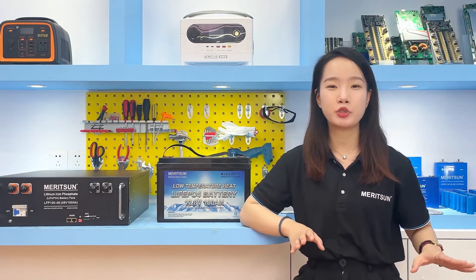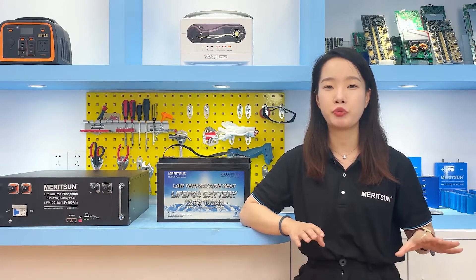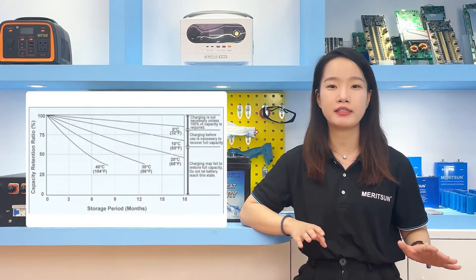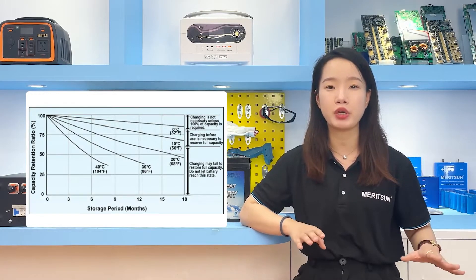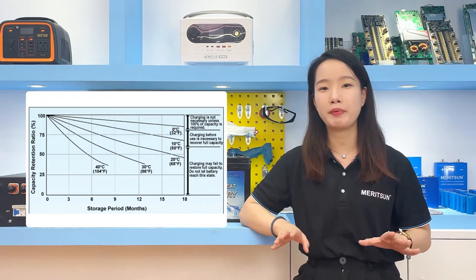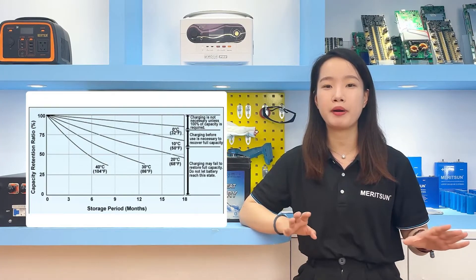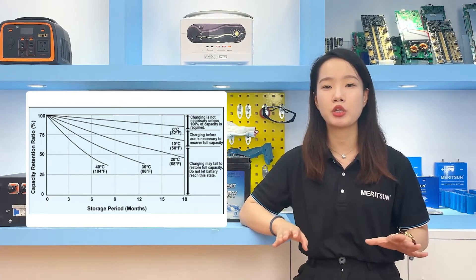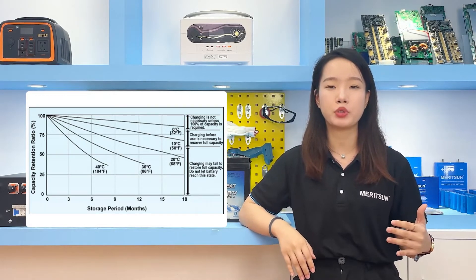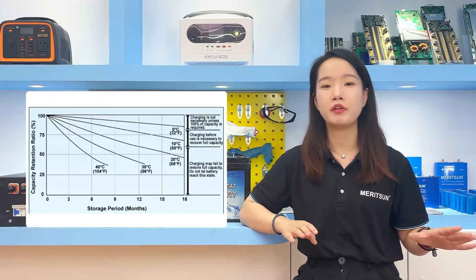Regarding battery self-discharge, it is non-linear with time, meaning the self-discharge rate changes with the passage of time. The self-discharge rate heavily depends on temperature: the hotter the battery, the quicker it self-discharges. Most lithium iron phosphate batteries have a self-discharge rate of 0.5% to 3% per month, meaning the battery will lose 0.5% to 3% of its charge per month. At low temperatures, this discharge rate will decrease drastically.